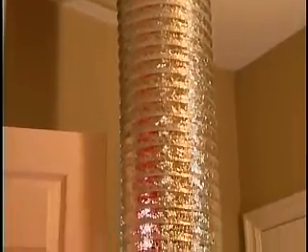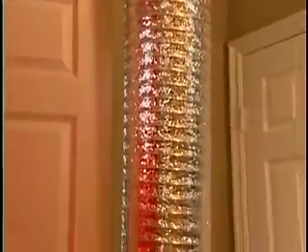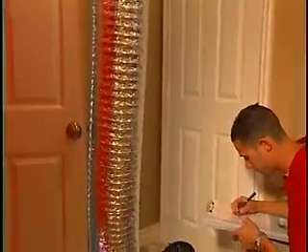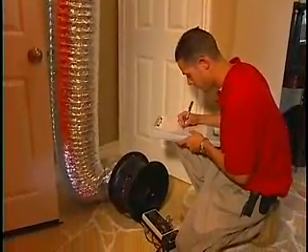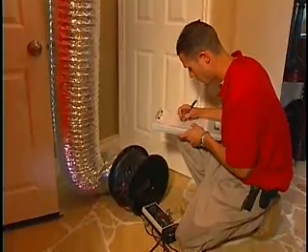A couple different ways that we can do that. We can use mastic sealants, or we can use UL-approved tapes. Now, how much do we seal them? Well, there's a test called a duct blast test that actually measures the amount of duct leakage. And in general, we never want to see our duct leakage much above 10% of fan flow. So let's say we have a 1200 CFM system. That means we'd never want to see our duct leaks be more than 120 cubic feet of air per minute.